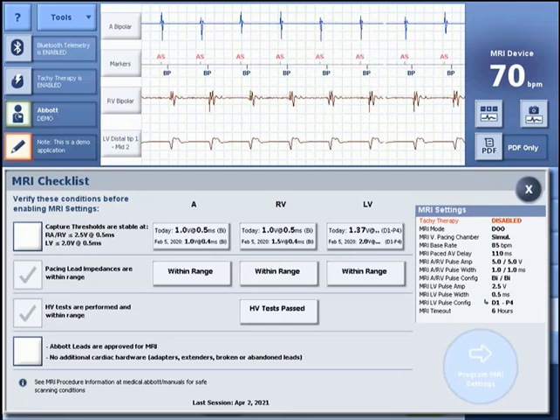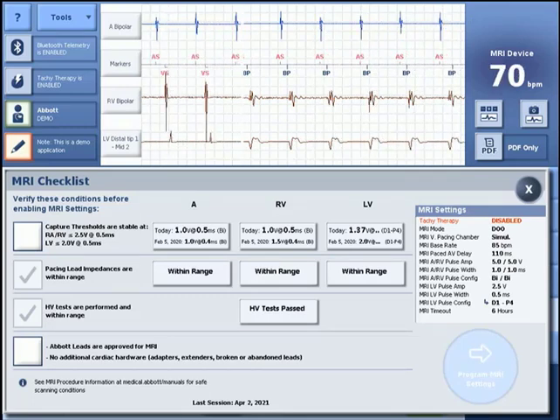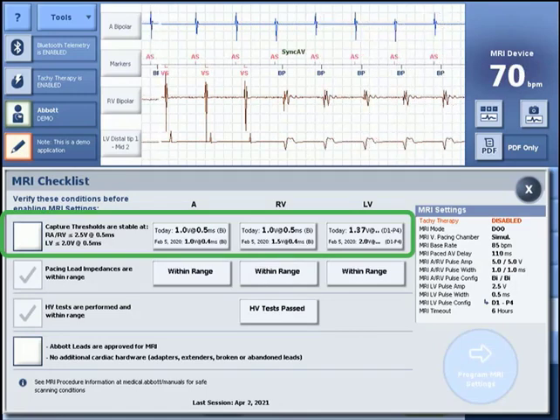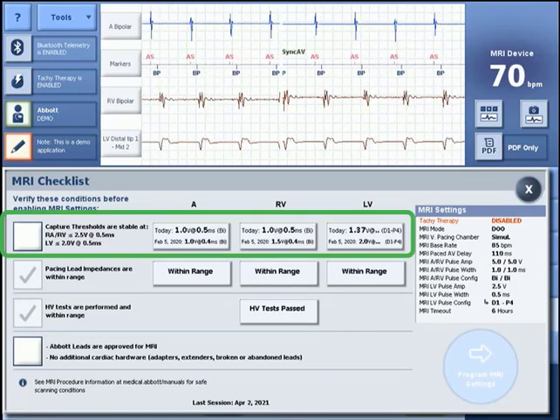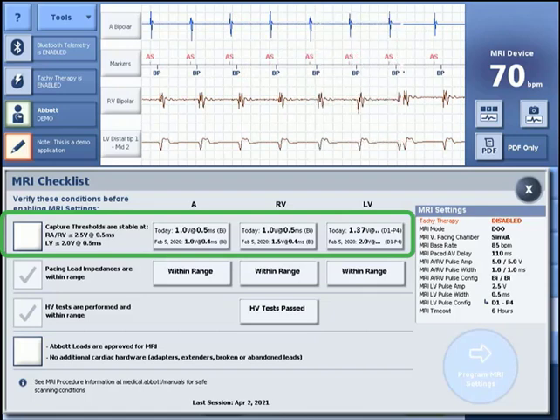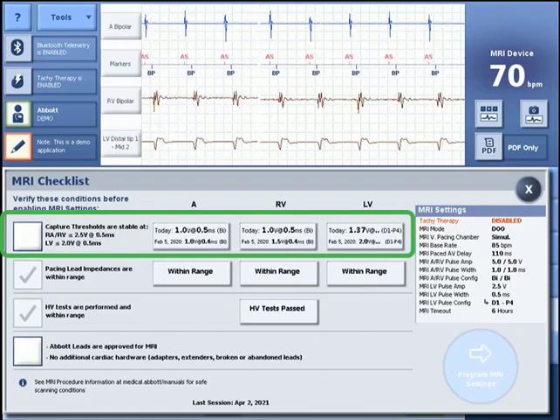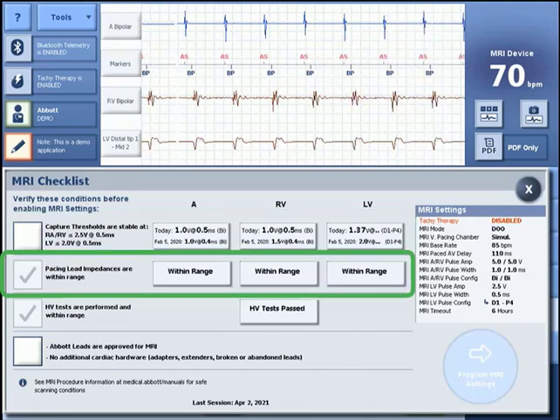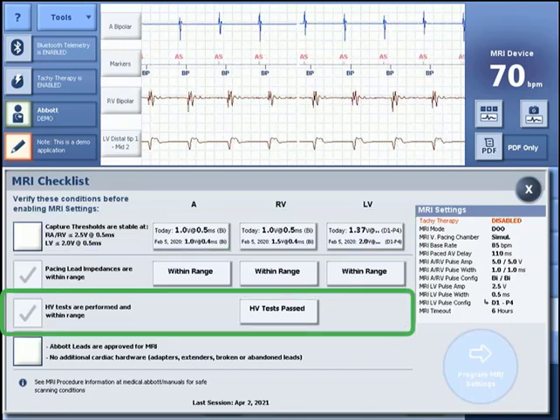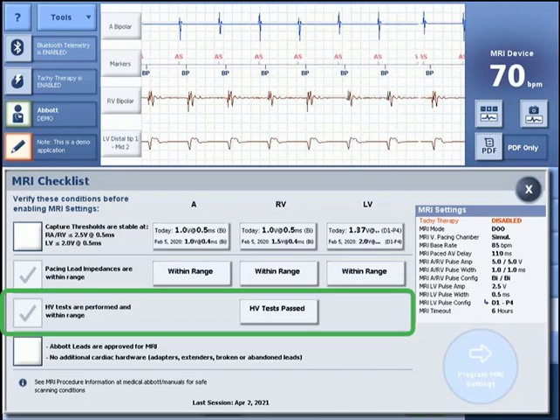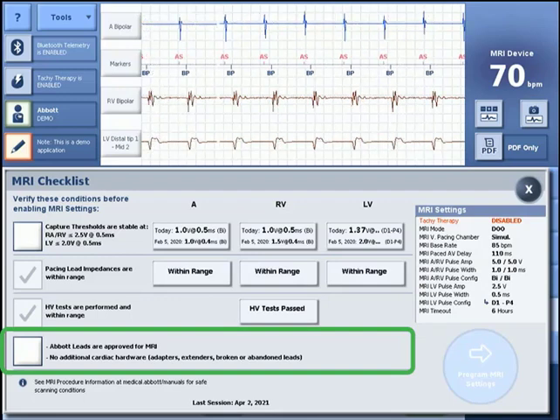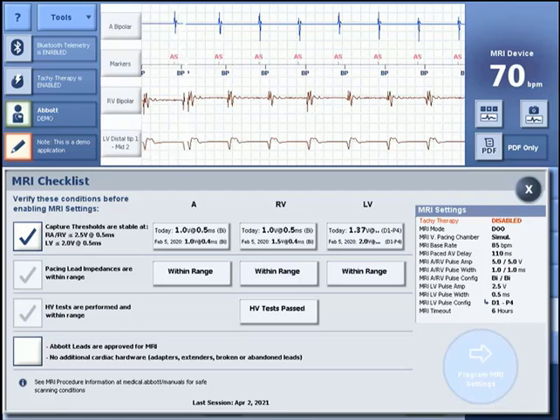The following conditions must be verified before MRI settings can be enabled: capture thresholds are stable at 2.5 volts or below at a pulse width of 0.5 milliseconds for RA and RV, and at 2.0 volts or below at a pulse width of 0.5 milliseconds for the LV lead. Pacing lead impedances are within range. High voltage tests are performed and within range. Leads are approved for MRI, and no additional cardiac hardware such as adapters, extenders, or abandoned leads are present.